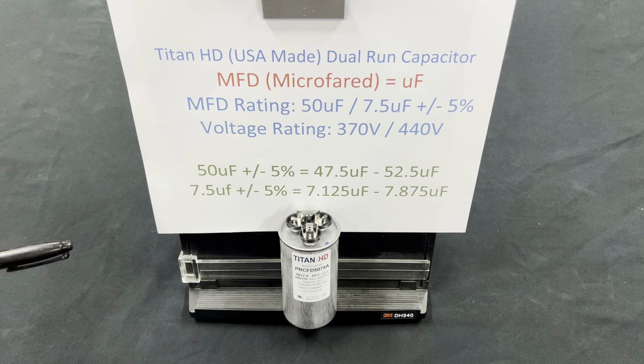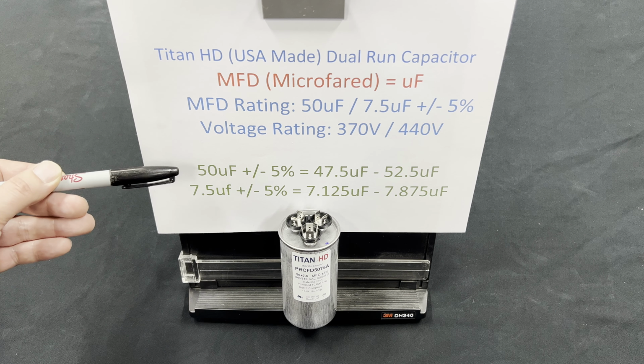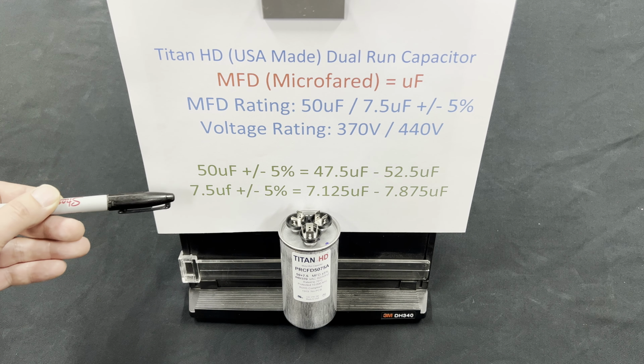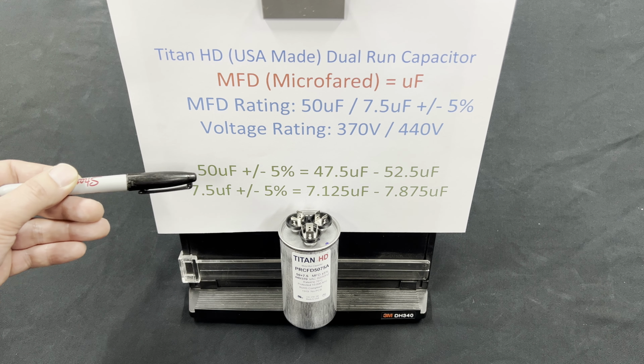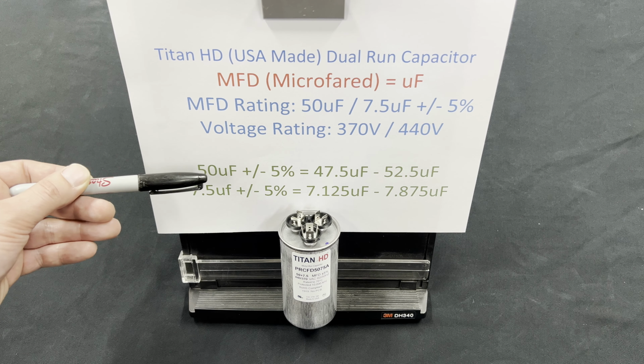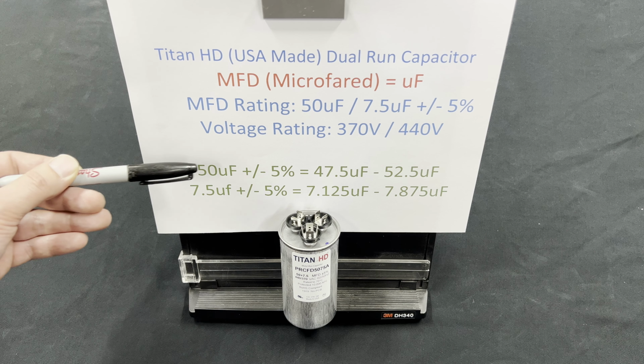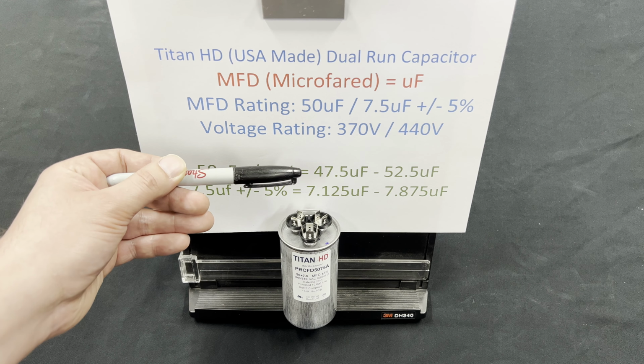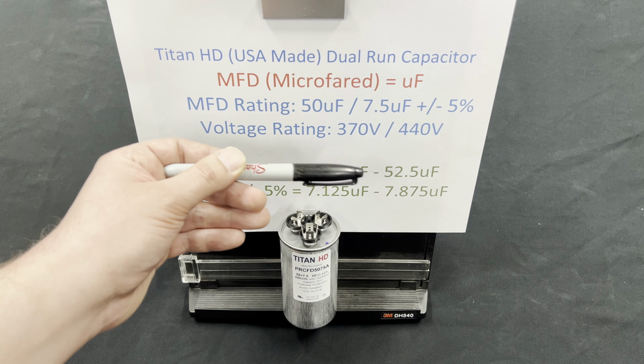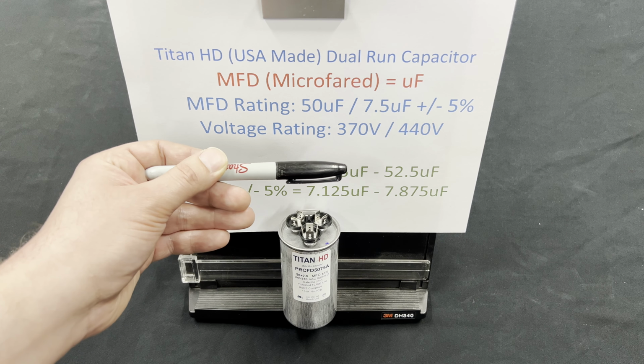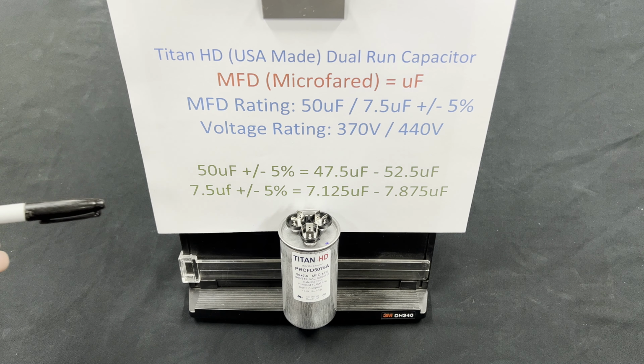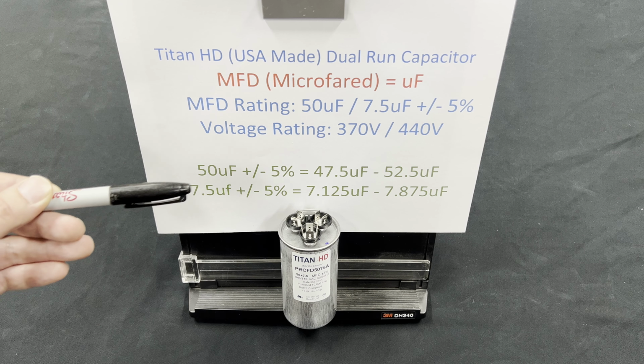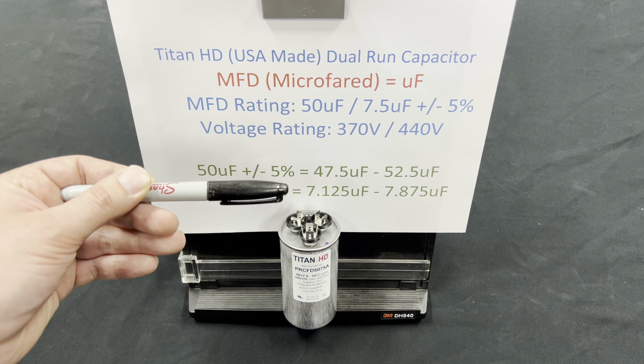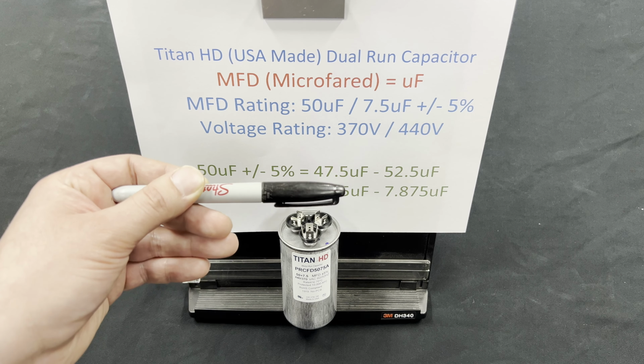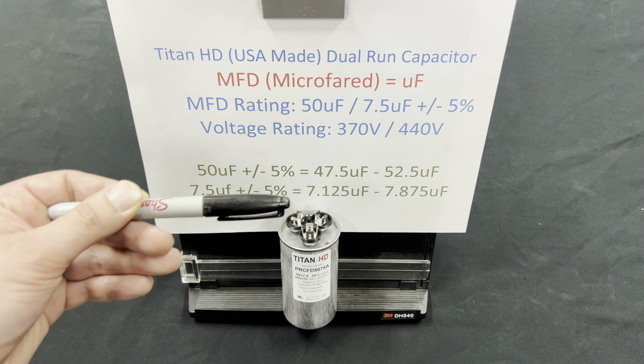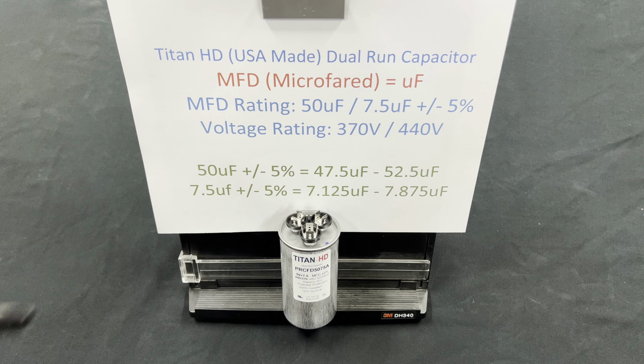Just to clarify the plus or minus 5%, even though the capacitor is rated at 50 and 7.5, it's allowed to be plus or minus 5% of that value. So 50 would mean that it could be as low as 47.5 UF or as high as 52.5 UF and still be considered a good capacitor. On the 7.5 UF, it would mean you can have 7.125 on the low or 7.875 on the high and have it still be considered a good capacitor.